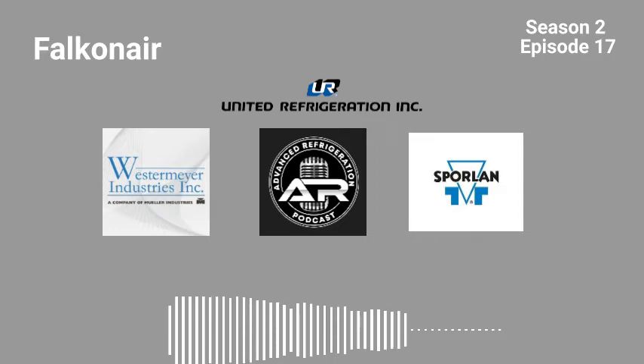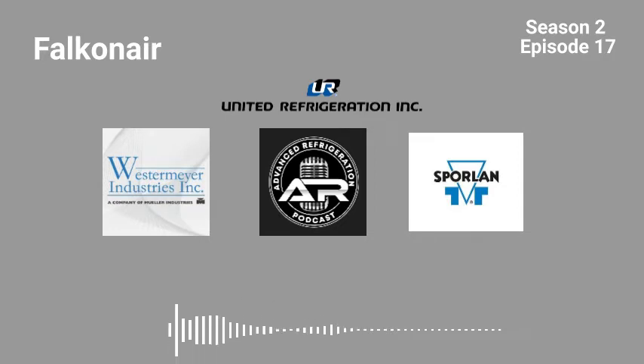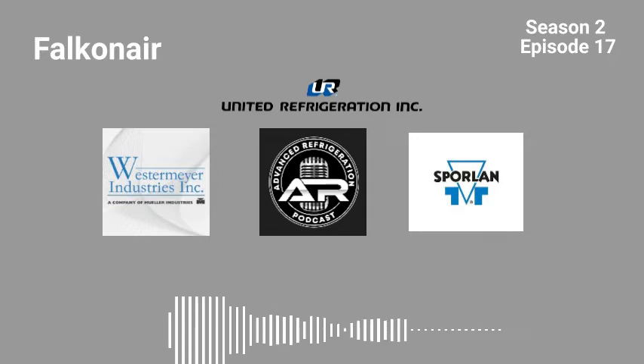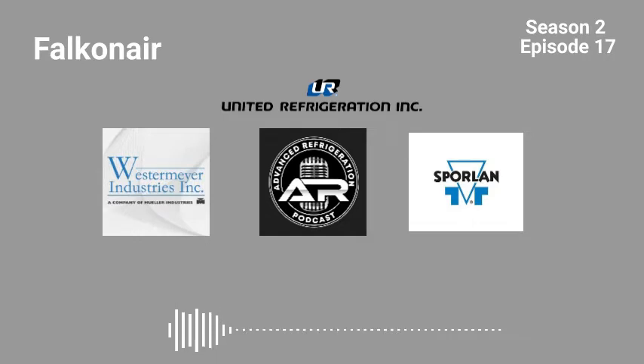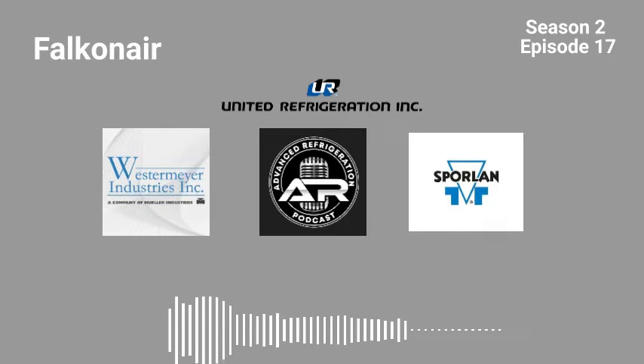We don't need it. You're just controlling it. Yes. Okay. And I'll tell you why. Because our algorithm will learn the behavior of your evaporator if it changes. So we know that ambient temperature changes. The temperature in your cooler changes because you brought in warm products. We also know that the thermostat can change. So you might commission the system when you require 35 degrees Fahrenheit, and then you decide, I want to go below 35 degrees Fahrenheit, I want to put it down to 30.